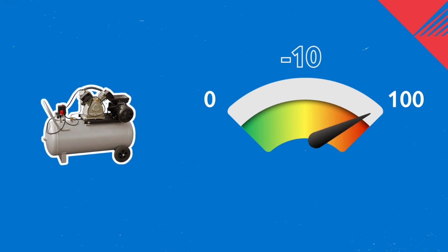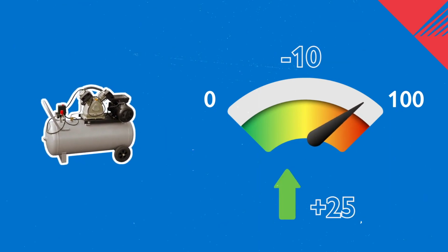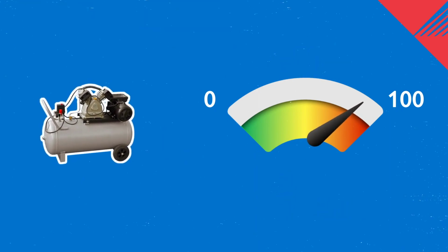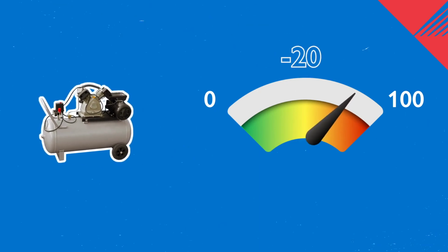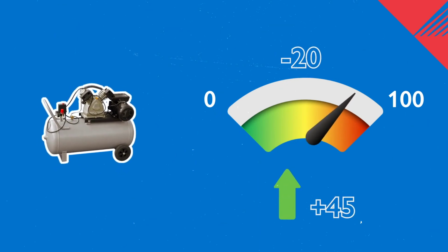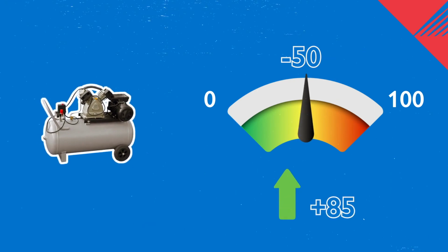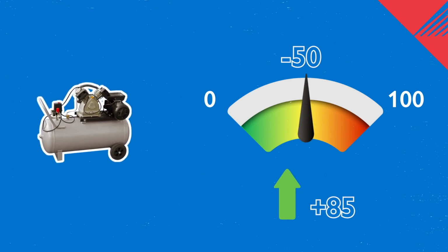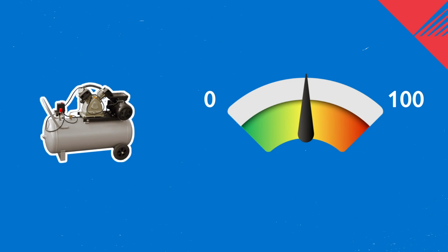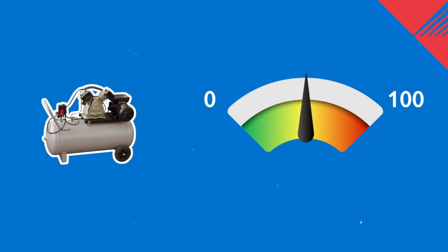If you dim the motor down by 10%, you save 25% of the energy. Reducing the speed by 20% offers you 45% energy savings, and if you give up 50% of speed, your system will save 85% on energy. As you can see, a VFD can offer significant savings.